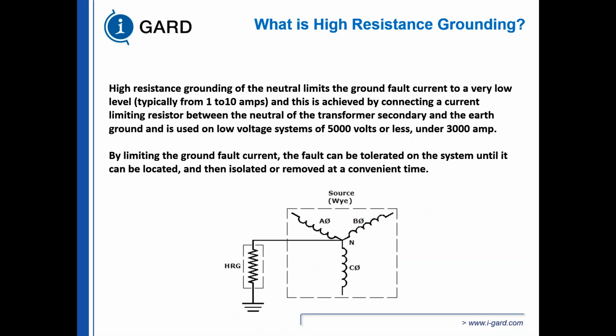High resistance grounding, if you limit the fault current on 4160 volts, 5 kV systems, to 10 amps or less is an arc flash mitigation technique. By limiting the ground fault current, the fault can be tolerated, and you can shut down in a timely manner, or you can keep the system working and find where the fault is with pulsing techniques.